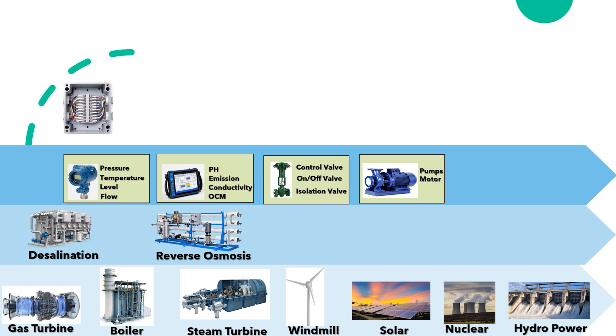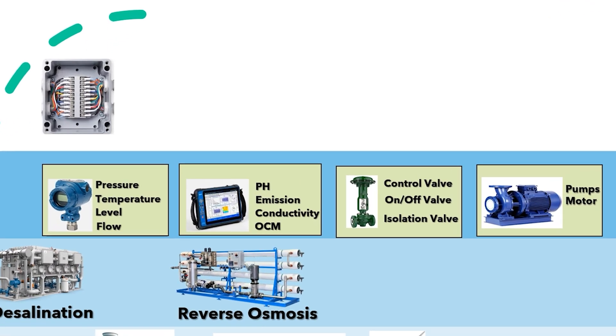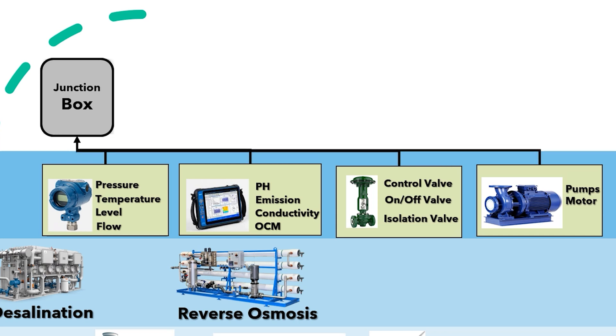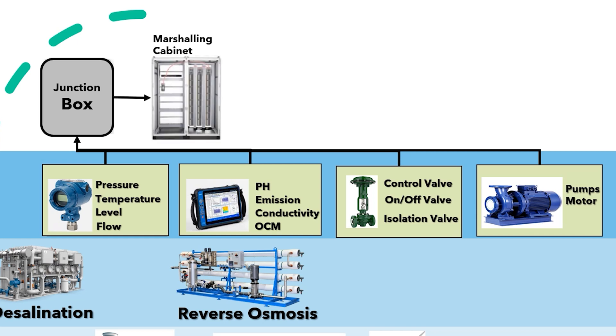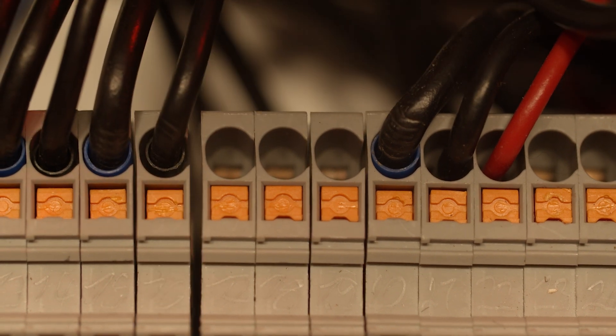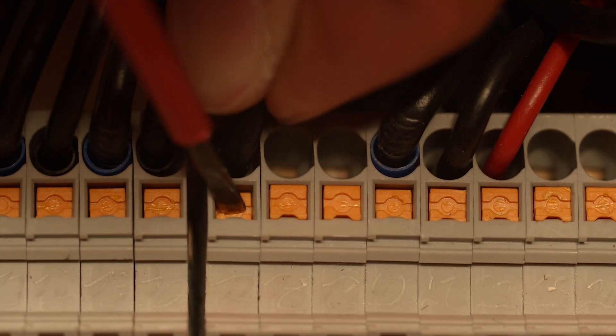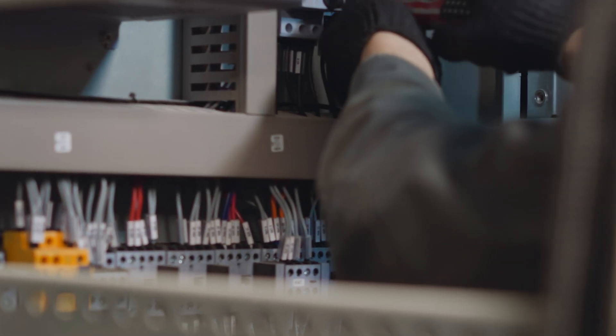All these devices need to send signals to the control room, so all instruments are wired to a local junction box. From the junction box, a common cable is sent to the marshaling panel. Marshaling panels provide cross-wiring functionality between field instruments and the control system. By having this type of interface, input and output issues can be quickly identified, and maintenance personnel can perform routine functions in the field without jeopardizing the heart of the control system.